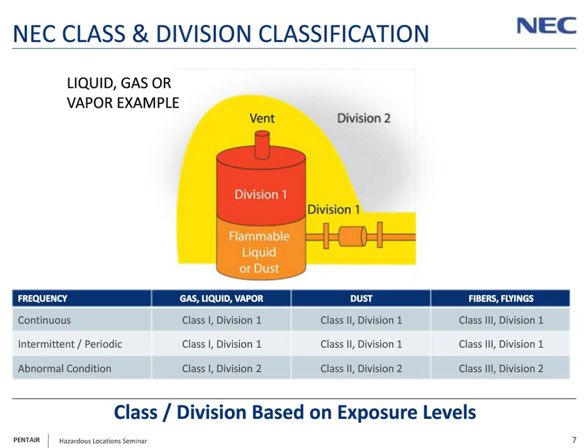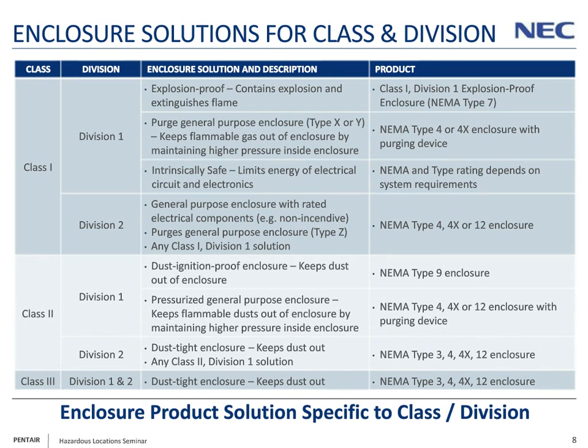So what types of enclosures and solutions can we use in different classes and divisions? This is a bit of an eye chart, but it's a good reference table to figure out what technologies you can use in different areas. So Class 1, Division 1, you have three options. You have explosion-proof, which is a traditional NEMA Type 7 enclosure, heavy cast, very well constructed enclosure with lots of bolts around it. I'm sure many of you are familiar with them. The idea here is that it allows explosions to actually occur within the enclosure, but it contains and extinguishes the flame and cools gases as it leaves.